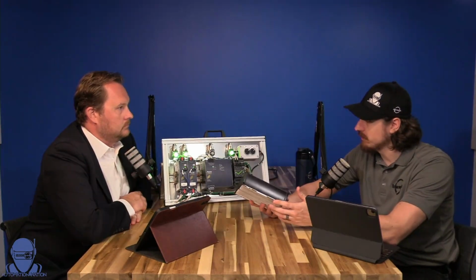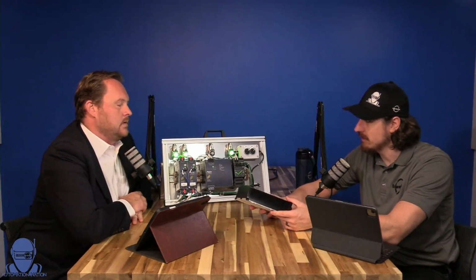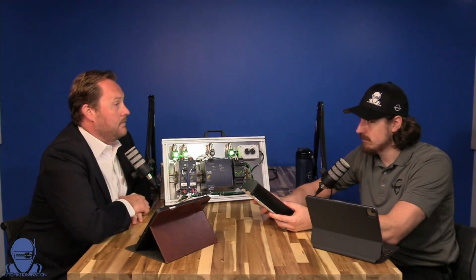And then the electronic circuit breaker that's built in on these, that's resettable over IO-Link. Yes, or button push on here. Configurable over IO-Link or in the field. And then you can also lock it out through IO-Link, so only authorized users can have the ability to reset or change a setting. And there's also a way to lock it out from the faceplate too. So again, only authorized users would have the ability to do that.